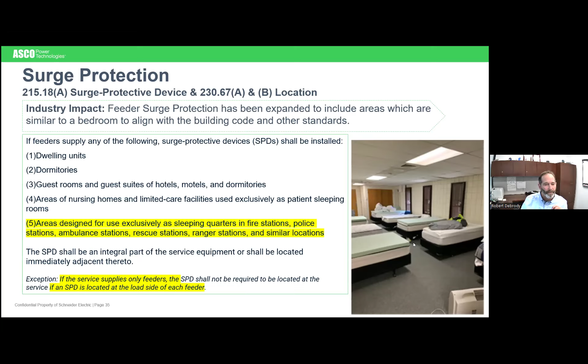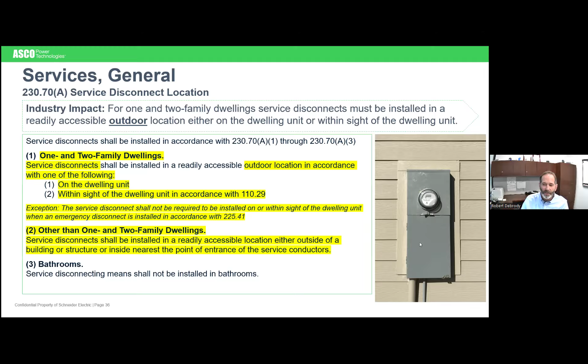Let's talk about service disconnects. Now, for 1 or 2 family dwellings, service disconnects must be installed outdoors. So this is something new. It used to not require it to be outdoors or mandated to be outdoors. And it can be outdoors on that dwelling or in sight of the dwelling in accordance with that one paragraph there. Other than 1 or 2 family dwellings, they say that it can be outside or at the point nearest the entrance nearest the point of entry of the service conductors. So they're just trying to make sure that in the case of a fire or something, that they have quick access. There's no confusion about how to turn that power off and where it's located, so they can quickly find it. Certainly understandable.